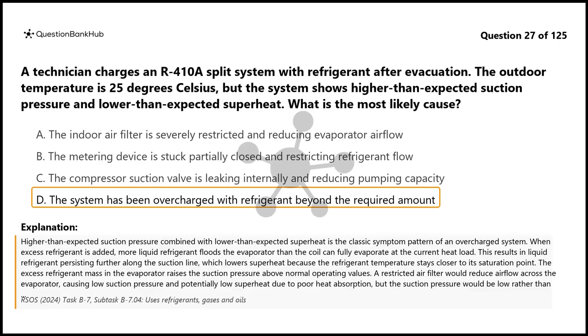A restricted air filter would reduce airflow across the evaporator, causing low suction pressure and potentially low superheat due to poor heat absorption, but the suction pressure would be low rather than high. A partially closed metering device restricts refrigerant flow to the evaporator, causing low suction pressure and high superheat. A leaking compressor suction valve would show high suction pressure but would typically show high superheat because the compressor cannot pull refrigerant through the evaporator effectively, so the distinction with overcharging is the superheat reading.